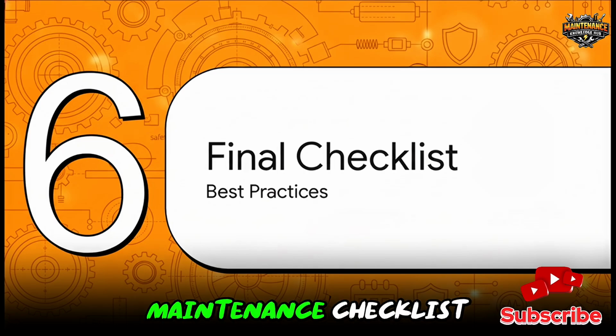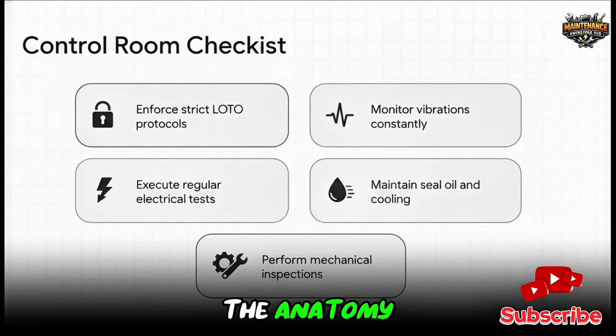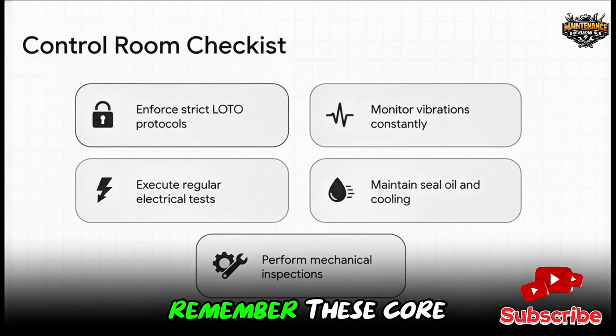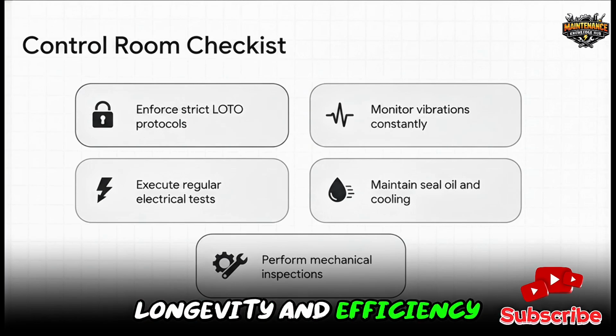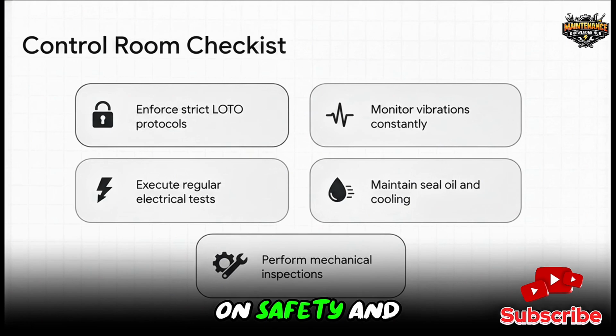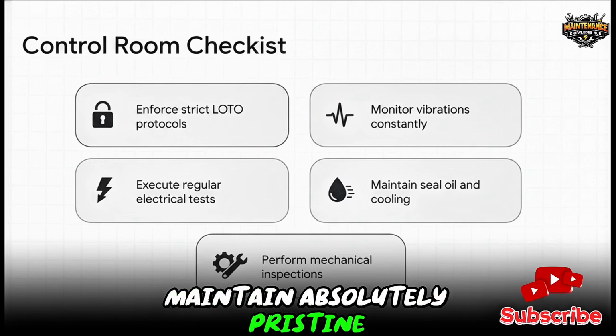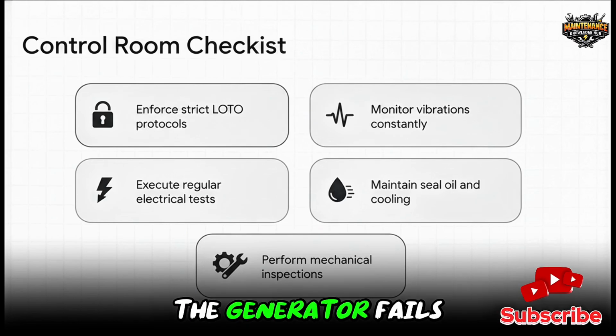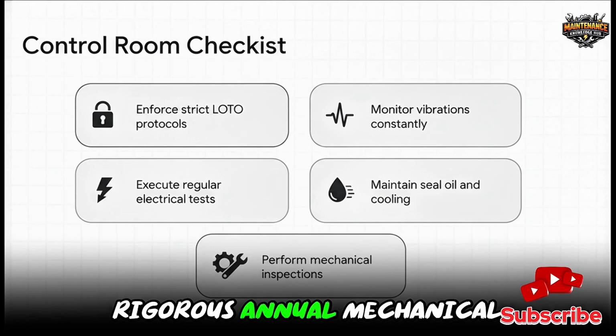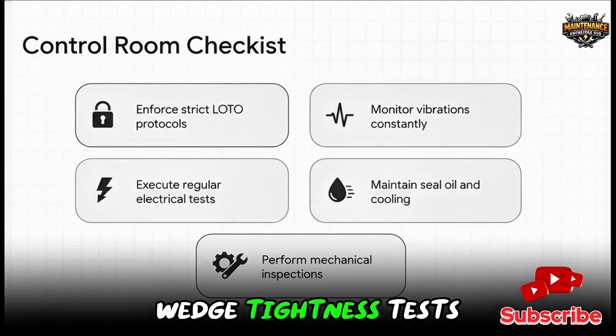Section 6. Final Maintenance Checklist. All right, we've covered the anatomy, the safety, the schedules, and the diagnostics. If you take literally nothing else away from this explainer, remember these core best practices for longevity and efficiency. 1. Never, ever compromise on safety and enforce strict LOTO and hydrogen protocols. 2. Perform continuous hawkish monitoring of vibration and bearing temperatures. 3. Execute regular electrical testing, particularly IR, PI, and earth faults, to catch insulation degradation before it becomes a failure. 4. Maintain absolutely pristine seal oil and cooling systems, because if they fail, the generator fails. And 5. Conduct rigorous annual mechanical checks, including those vital air gap and wedge tightness tests.